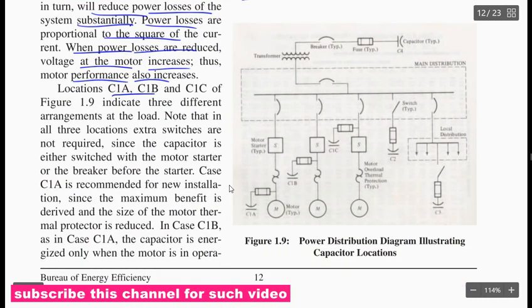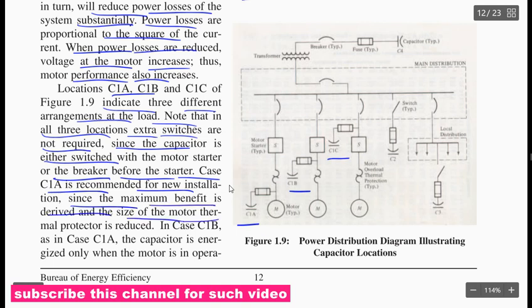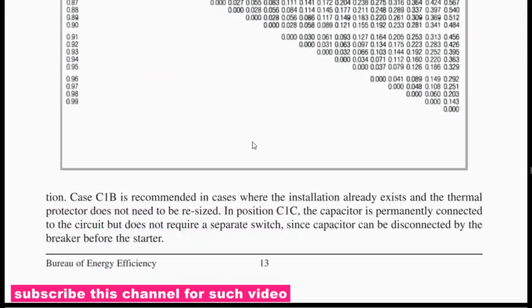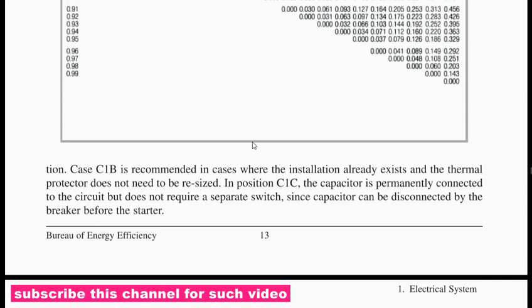In the figure, C1A, C1B and C1C indicate three different arrangements of the load. Note that in all three locations extra switches are not required, since the capacitor is either switched with the motor starter or the breaker before the starter. Case C1A is recommended for new installations, since the maximum benefit is derived and the size of the motor thermal protector is reduced. In Case C1B, the capacitor is energized only when the motor is in operation. Case C1B is recommended where the installation already exists and the thermal protector does not need to be resized. In position C1C, the capacitor is permanently connected to the circuit and does not require a separate switch.